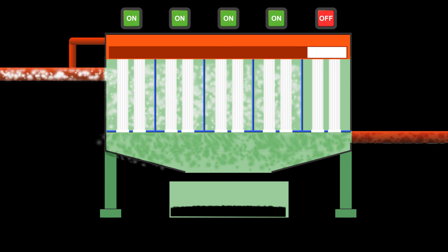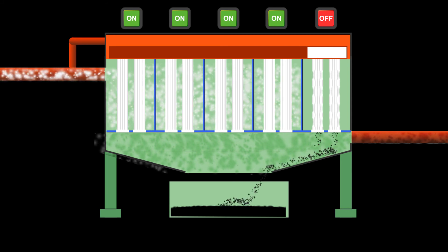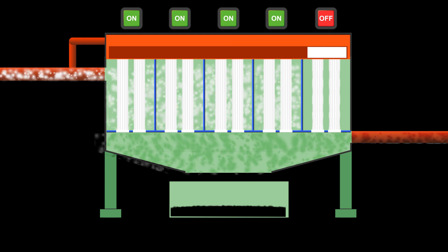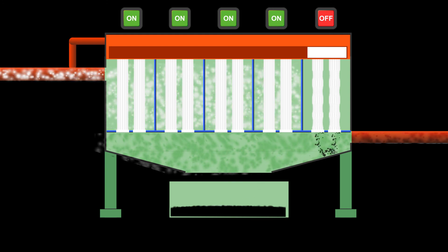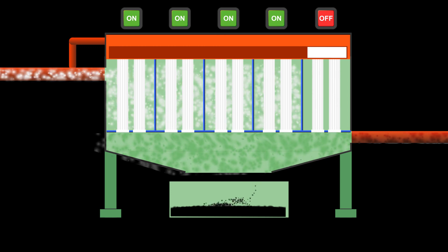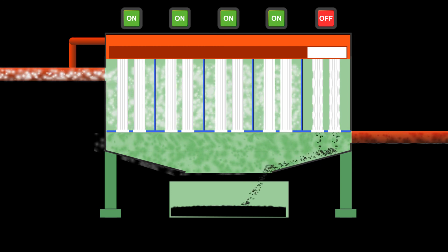Once activated, the pressure from the reverse air flow also causes the filter bags to slightly collapse. These types of reverse air bags have sewn in rigid rings that allow them to flex but not collapse completely or pancake during the cleaning cycle.